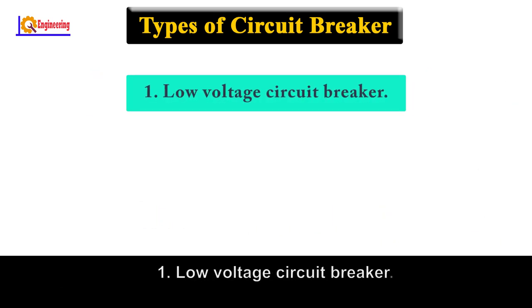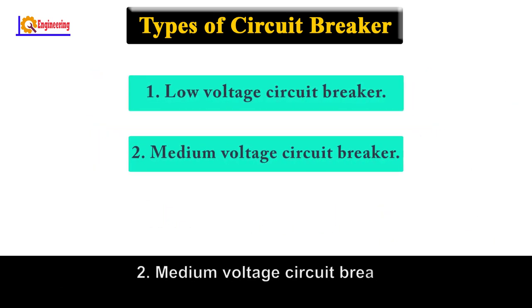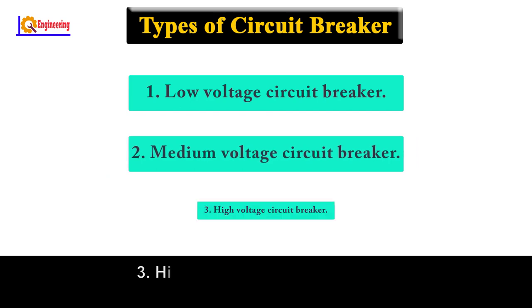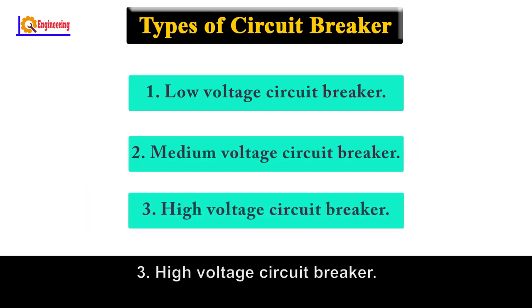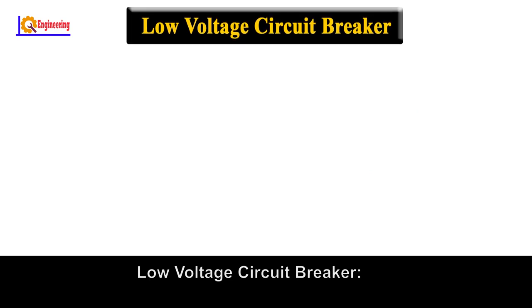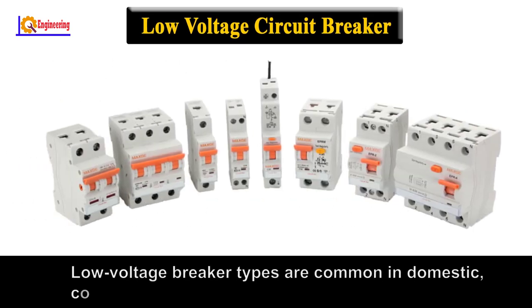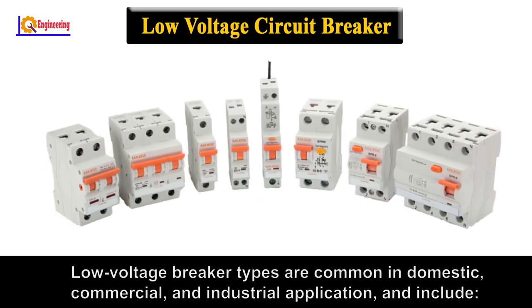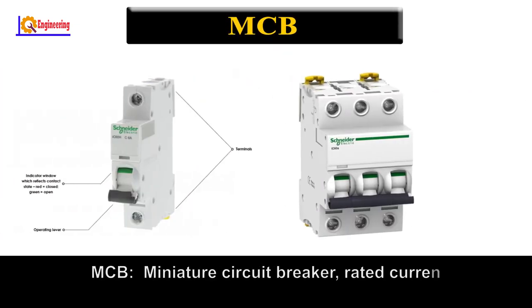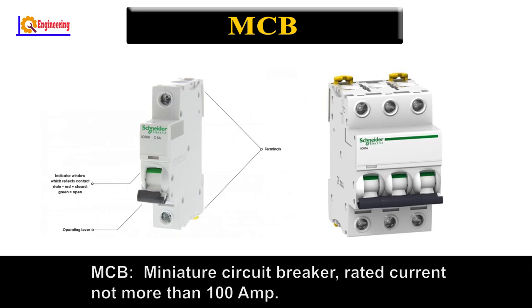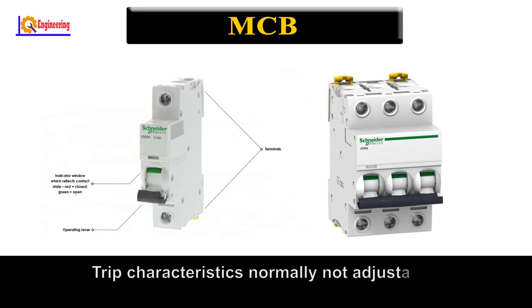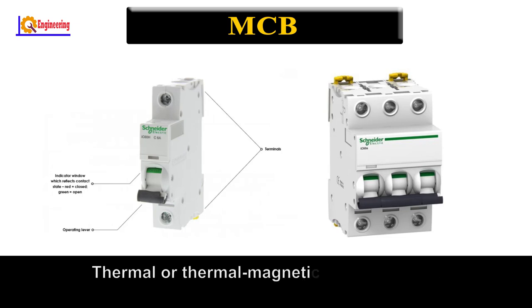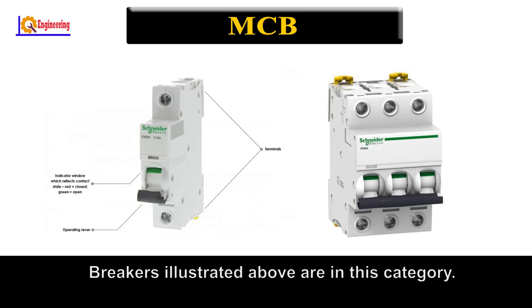Number one: Low voltage circuit breaker. Number two: Medium voltage circuit breaker. Number three: High voltage circuit breaker. Low voltage circuit breaker types are common in domestic, commercial, and industrial applications. MCB — Miniature Circuit Breaker: rated current not more than 100A, trip characteristics normally not adjustable, thermal or thermal-magnetic operation. Breakers illustrated above are in this category.